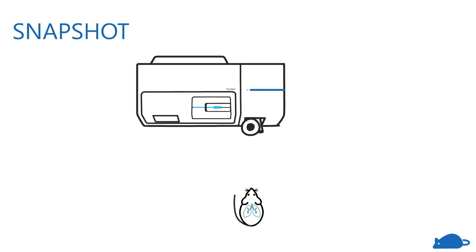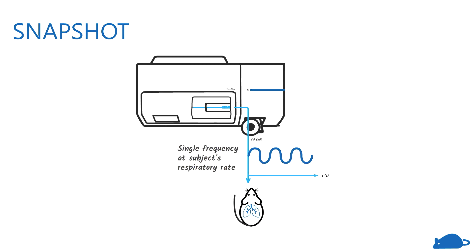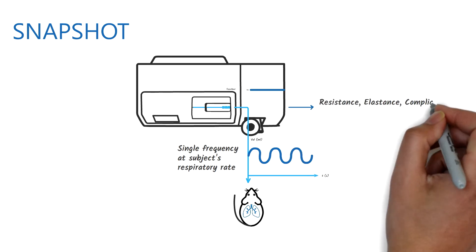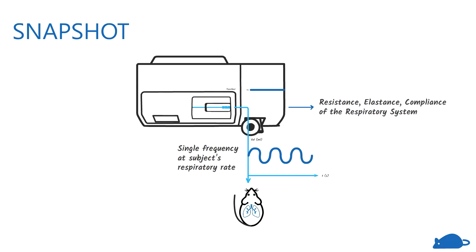In the snapshot measurement, the lungs are given a single frequency signal matched to the subject's respiratory rate. Using the signal, the flexiVent calculates the resistance, elastance, and compliance of the respiratory system.